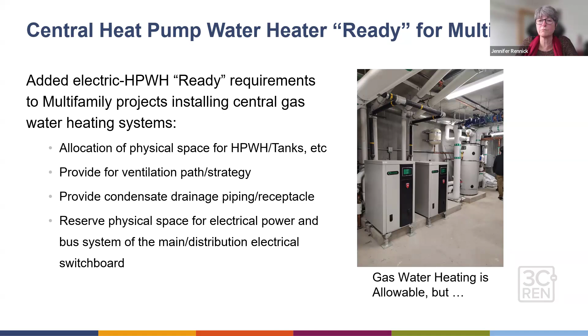But central heat pump water heater ready for multifamily is new. So they added these requirements. So in other words, you can do gas water heating, like is in the image there. It's allowable, but you need to make sure that that space is big enough for the heat pump water heater and the tanks, and you need to provide for the ventilation strategy and the pathways, provide for the condensate drainage, and make sure that there's reserved physical space in the electrical panel or the main distribution electrical switchboard.